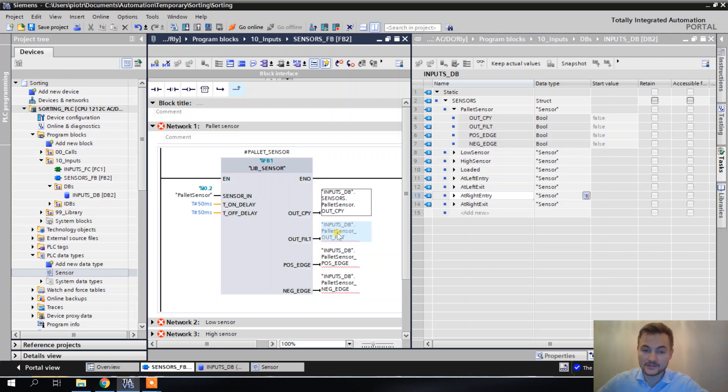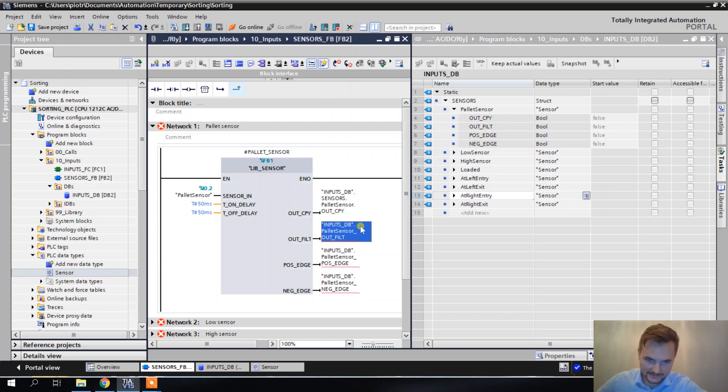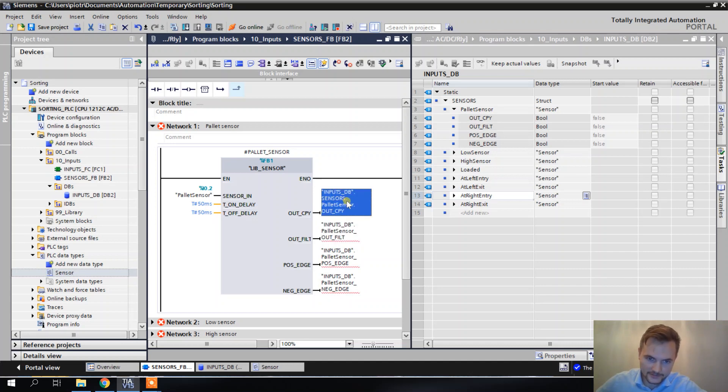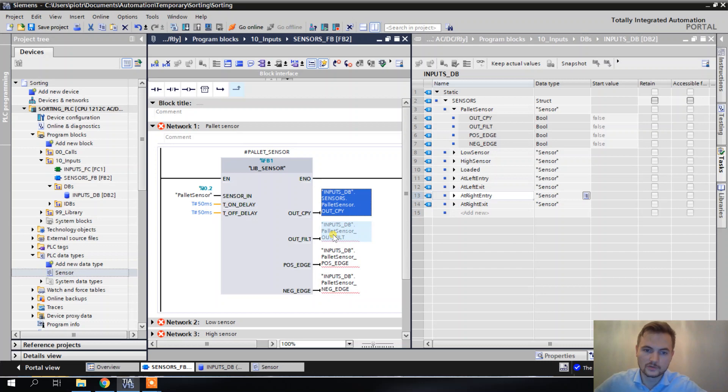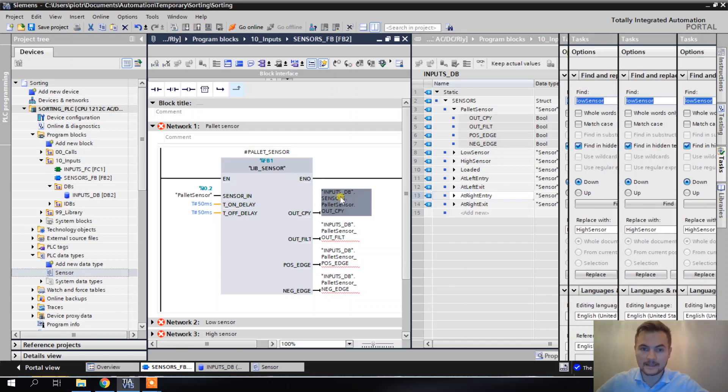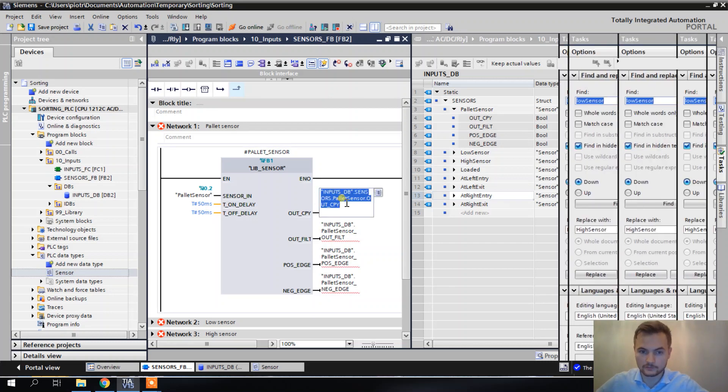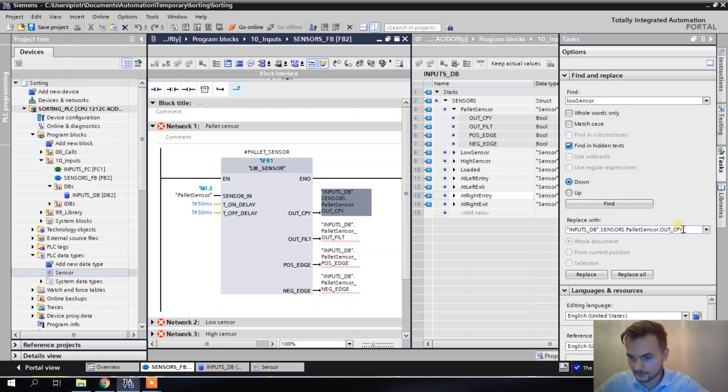So now I'm going to create a sensor tag for each of the sensors. And now to use the replace function, I need to know exactly what I need to replace. Let's have a look at the difference between this tag and this tag. So we have a new part here, which is sensors dot. So instead of inputs db dot sensors dot, we used to had inputs db dot. So it's going to be very easy to replace. And then I will have to replace one more thing.